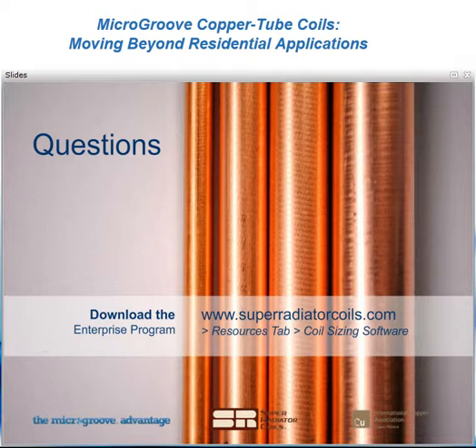All righty. Next one up here is, what is the largest coil you can manufacture with 5mm copper tubing? I'll take that one. I would answer that in two ways, large being physical size or capacity. For physical size, we've designed and built coils up to over 100 inches long using the 5mm diameter tubing. It starts to look like a long piece of spaghetti, but it does work. We've developed the techniques and practices to do that. There really is no limit on the depth of rows. That's proven to be a very nice advantage.